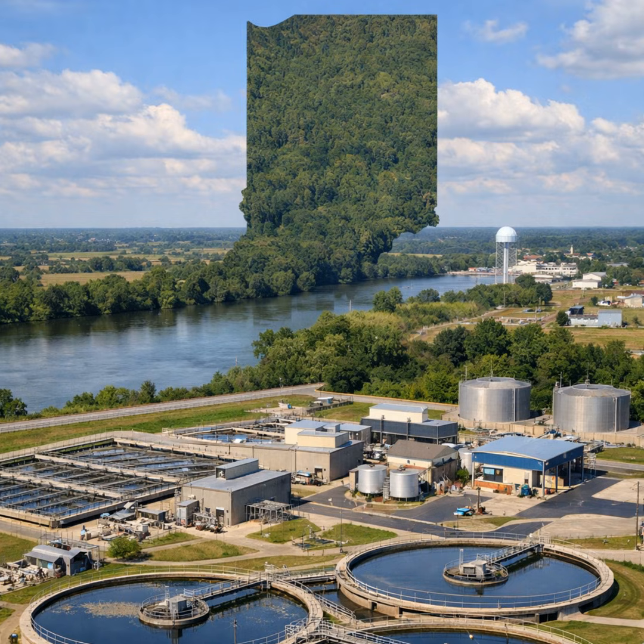Total dynamic head, TDH. When a pump is lifting or pumping water, the vertical distance in feet or meters from the elevation of the energy grade line on the suction side of the pump to the elevation of the energy grade line on the discharge side of the pump. The total dynamic head is the static head plus the pipe friction losses.